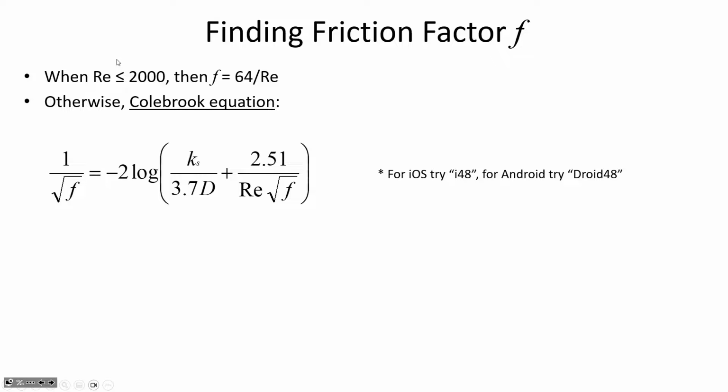In that rare case, maybe the water's flowing through a pipe at such a small velocity that conditions are laminar, but there's so little friction loss during that low flow condition that we don't really care what the F value is. And so you won't ever design the governing case using a friction factor with this 64 divided by the Reynolds number.